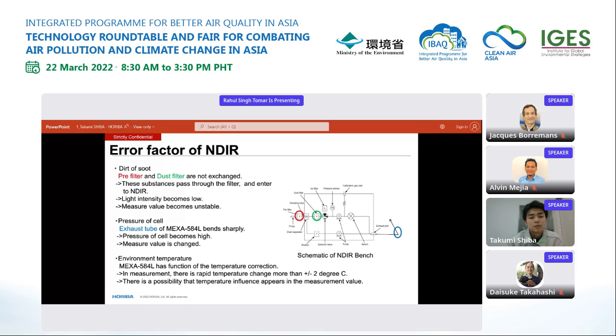The second is the pressure inside the detector. If the exhaust tube of the device bends at an acute angle, gas will not flow and pressure will be applied inside the device. Higher pressure in the detector can cause the measurement to change, resulting in error.